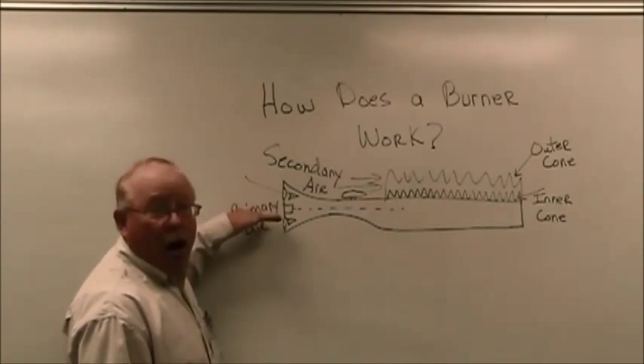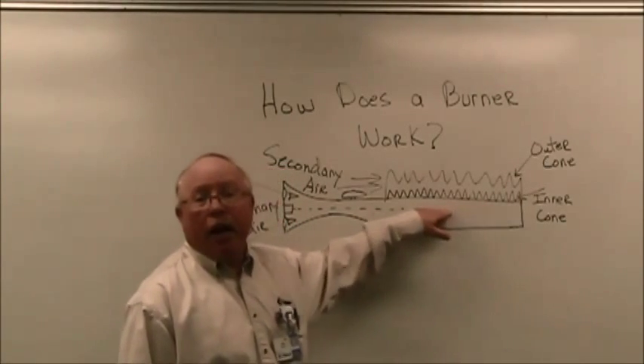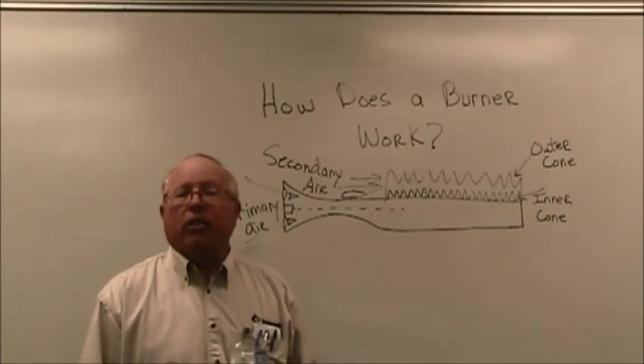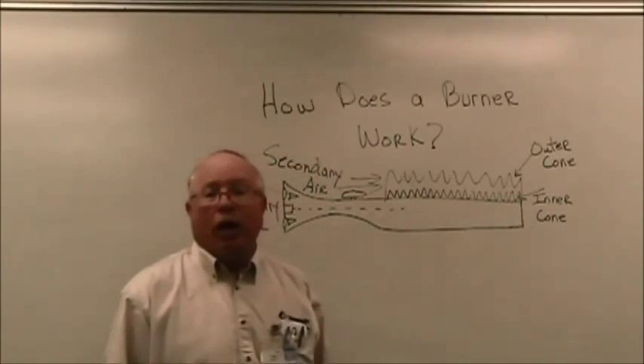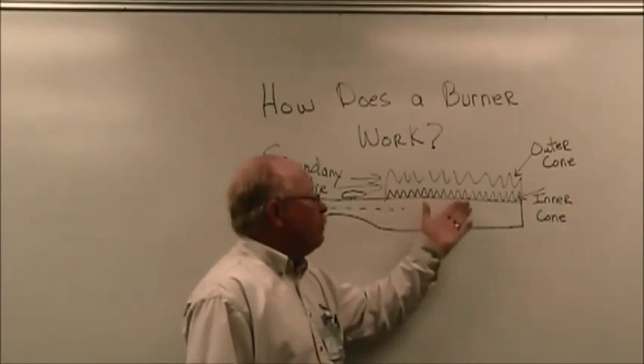The air and the gas travel through the venturi throat and into the mixing chamber. Here, the gas and the air are going to be mixed together thoroughly, and then they're distributed evenly through the ports of the burner. An ignition source lights off the gas, and then the gas burns.